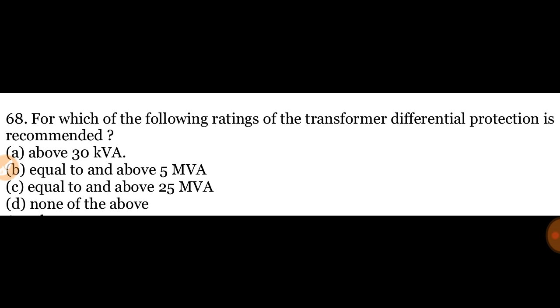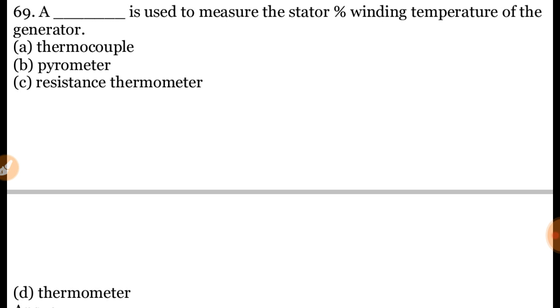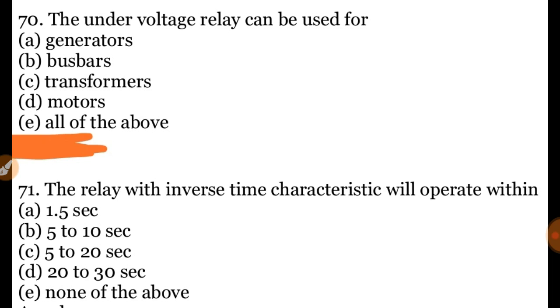For which of the following rating of the transformer is differential protection recommended? Above 30 kVA, equal to and above 5 MVA, equal to and above 25 MVA, none of the above. Answer is equal to and above 5 MVA. 69 question. A dash is used to measure the stator percentage winding temperature of the generator. Thermocouple, pyrometer, resistance thermometer, thermometer. Answer is resistance thermometer.